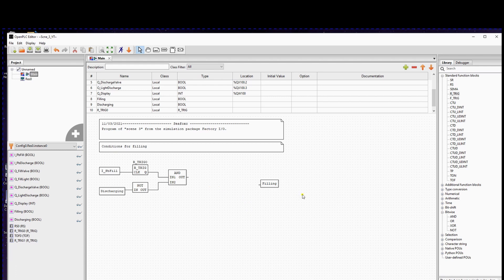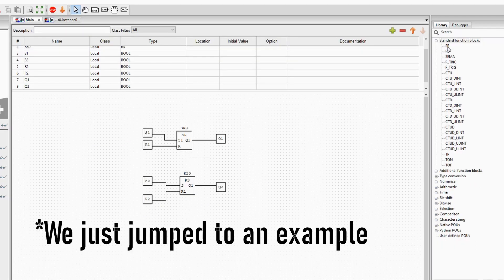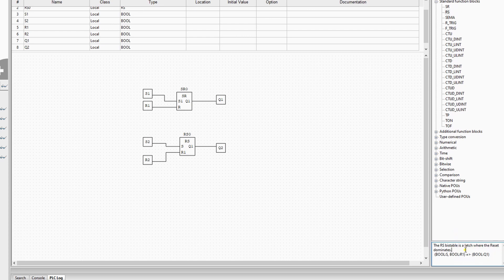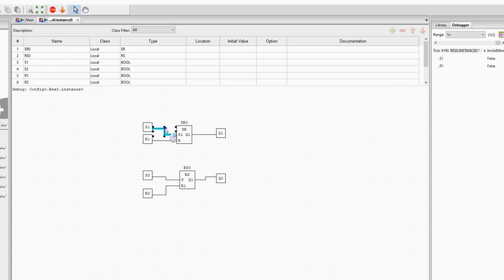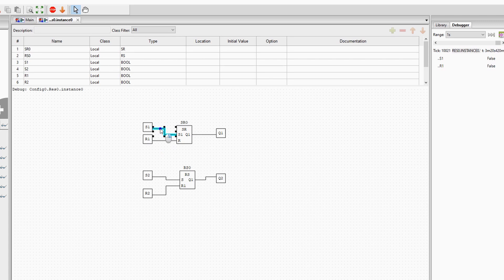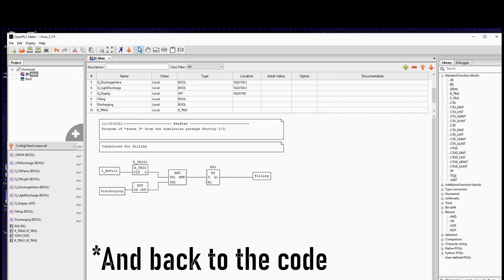To do this we'll use the RESET SET function block. You have two function blocks to do this: the SET RESET block and the RESET SET block. The PLC editor will give you some basic info about the block when you hover the mouse over it. If the S signal of the block is true, the output will be set to true, and it will stay true even when the S signal becomes false again. If you set the R signal to true, the output will be set to false. The difference between the SET RESET and RESET SET block is the priority: if both S and R are active, SET RESET gives priority to SET, while RESET SET gives priority to RESET.